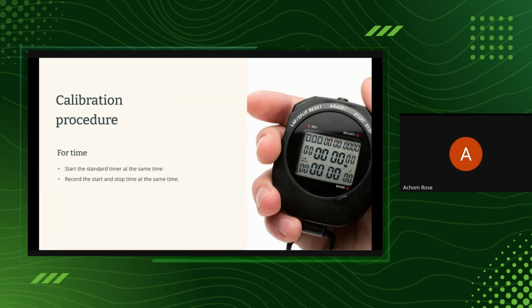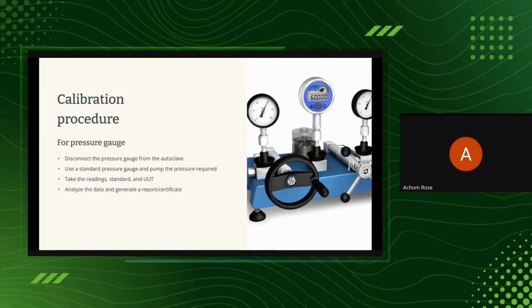Then for the pressure gauges, like I said, sometimes you may want to calibrate the pressure gauge to be sure that the indication of the pressure gauge is a reflection of what is inside the chamber. So you have to disconnect the gauge from the autoclave, and then we use a standard pressure gauge, which is this in the middle. So we have our pressure gauges that we want to calibrate. So you pump the pressure, whatever is reading here, you compare it with what is reading on this side. So because of hysteresis, we normally calibrate going upwards, maybe from 0 to 10 bars, and then also again from 10 to 0 bars. So we do up and down to cover for hysteresis. Okay? And then you analyze and generate a report.